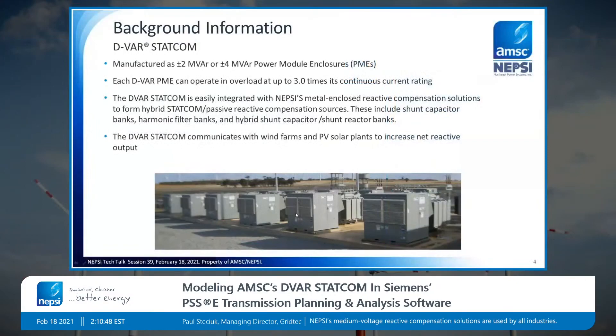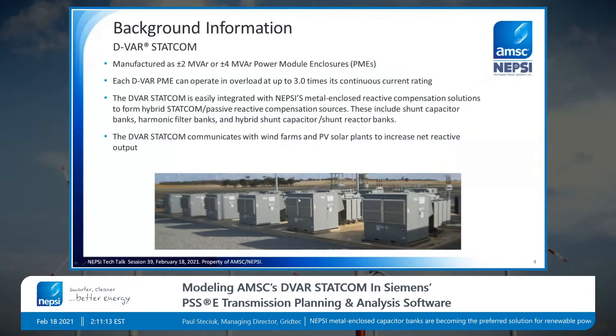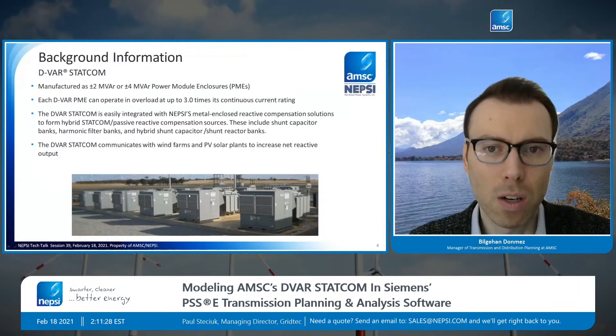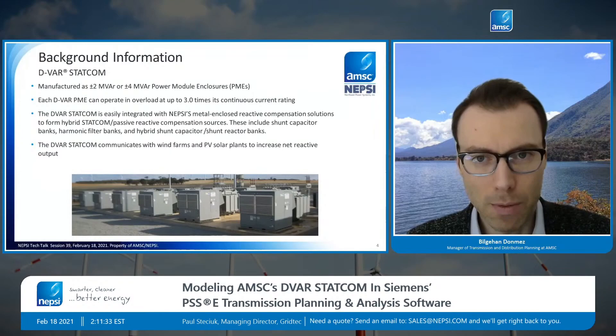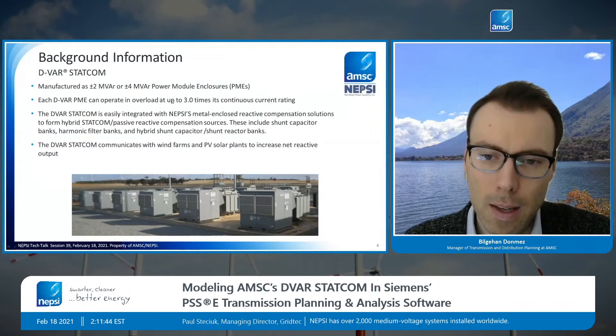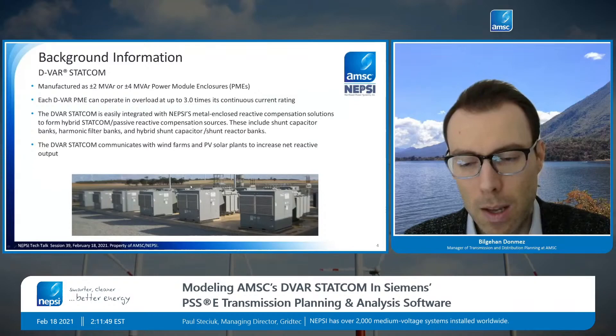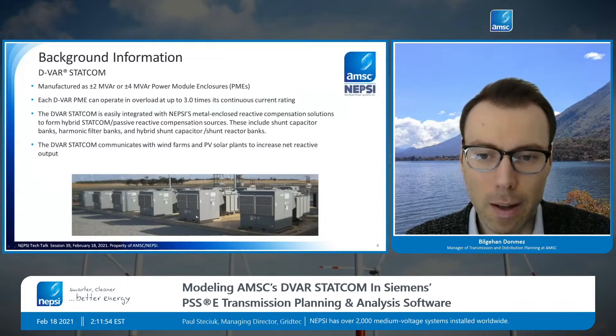One of these boxes is our modular 4 megavar unit — what we call PMEs, or power module enclosures. Inside each box you have 4 MVA worth of inverters, and these boxes can be half-populated to get a 2 megavar unit. You can put as many as you want to scale it up and down. One unique thing about these inverters is they have up to 3 times the current rating as overload. So a 4 megavar module can produce 12 megavars at 1 per unit — it's really 3 per unit current. Unlike a capacitor, which is a constant impedance device, the STATCOM is a constant current device.